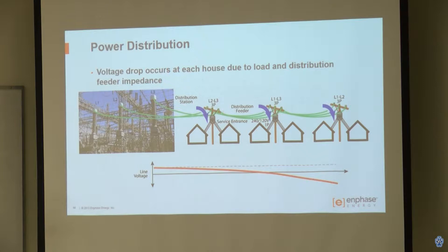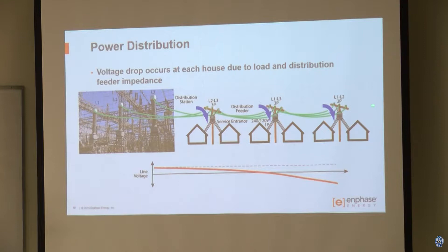Looking at the distribution system: we have a distribution station with distribution feeders and transformers. People call them cans because they look like a can — they feed each house. The transmission lines are in the hundreds of thousands of volts; distribution feeders are thousands of volts; and in-house we're down to hundreds of volts. As you work your way further down the feeder, the voltage drops — because at each node we're pulling current, and at each successive node the cumulative current increases, so we get a voltage drop building up.